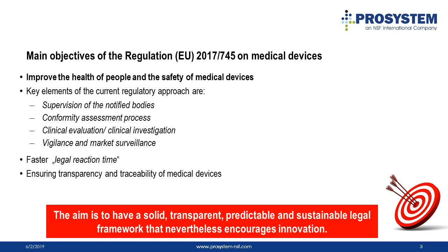The objective of this revision of the European Medical Device Regulation is to improve the protection of health and the safety of medical devices. Nevertheless, the fundamental regulatory model remains unchanged, including supervision of notified bodies. However, the notified bodies need to be redesignated. The conformity assessment process and risk-based review, clinical data, vigilance, and market surveillance are still required. MDR also defines a faster legal reaction time for adverse event reporting, both for manufacturer and competent authorities.